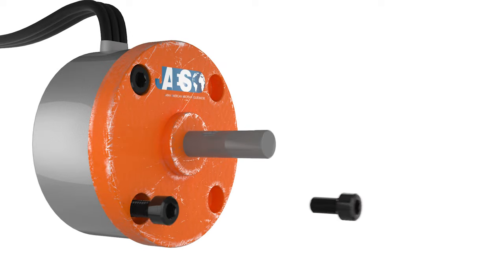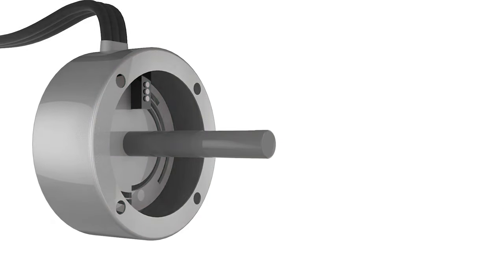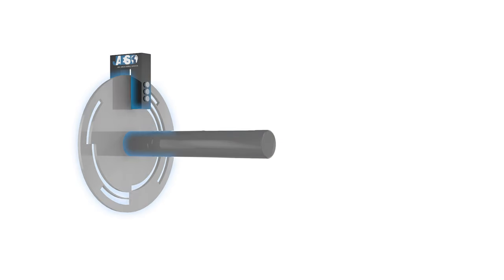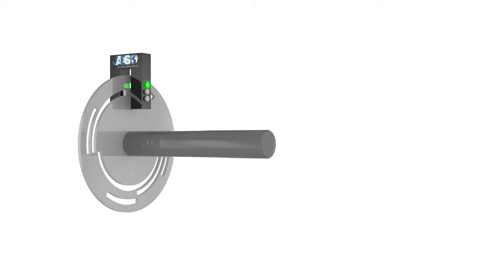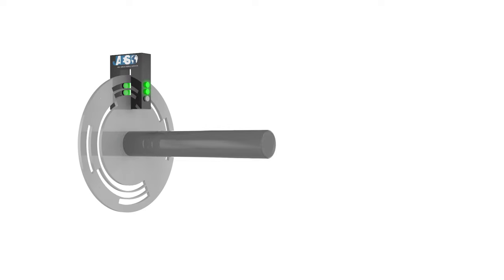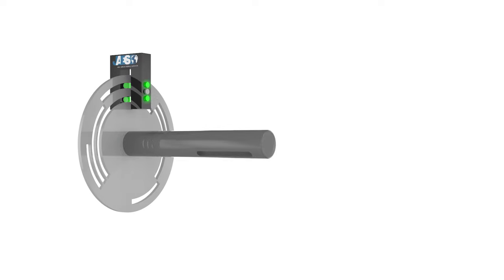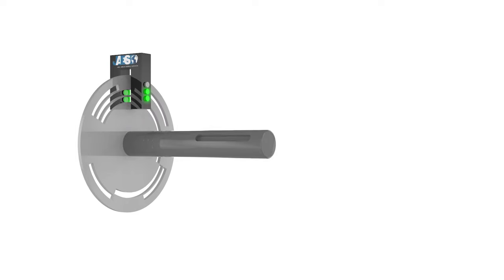Here's an example of an absolute rotary encoder. We can see inside that a slotted disc on a shaft is used in conjunction with a stationary pickup device. When the shaft rotates, the disc is rotated in a beam of light, such as an LED, and the markings on the disc act as shutters, blocking and unblocking the light.